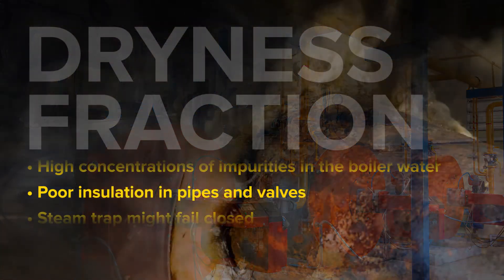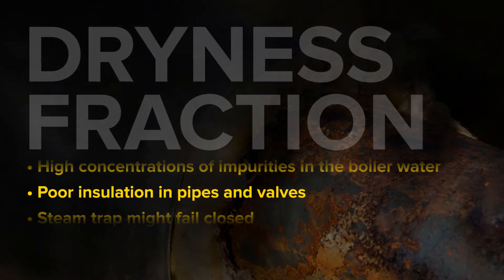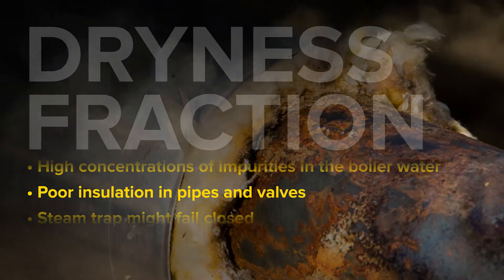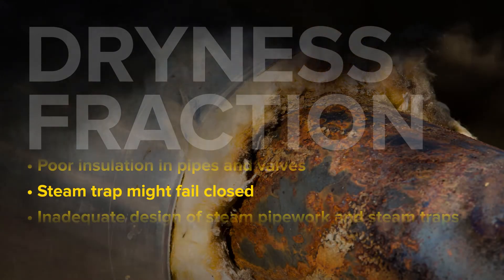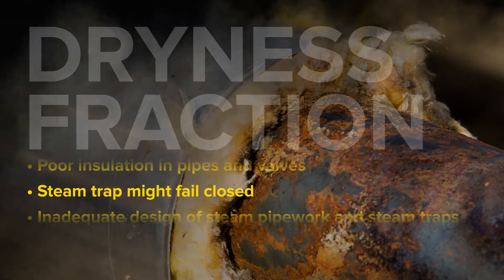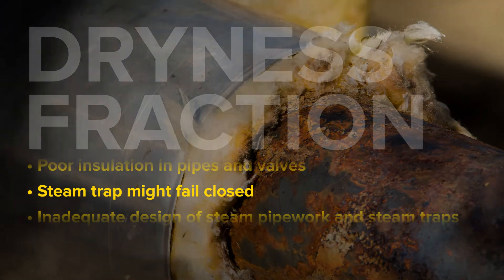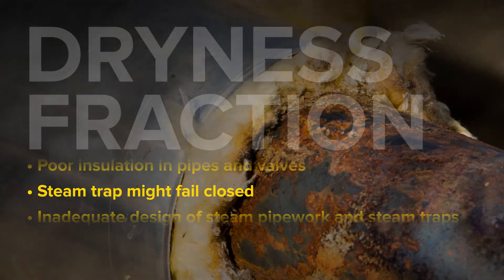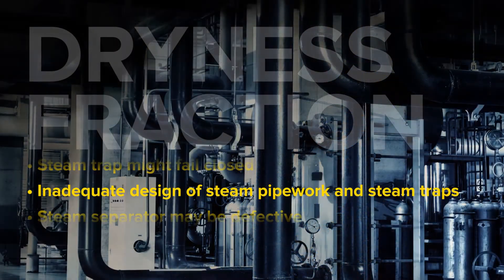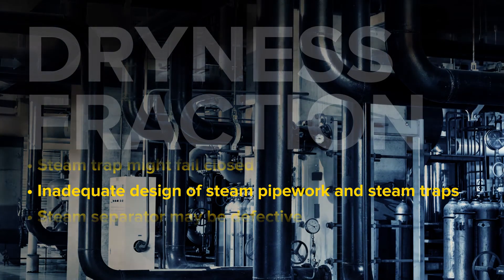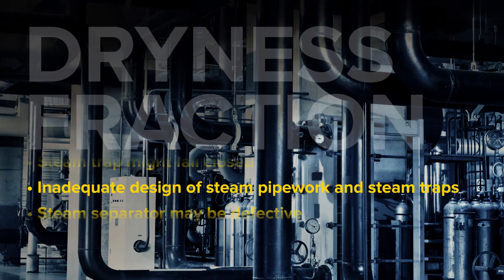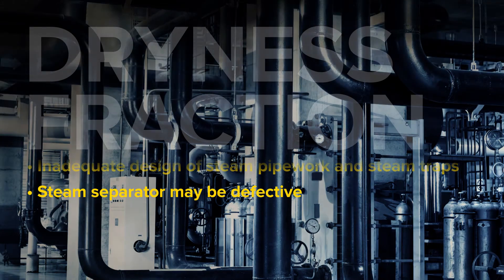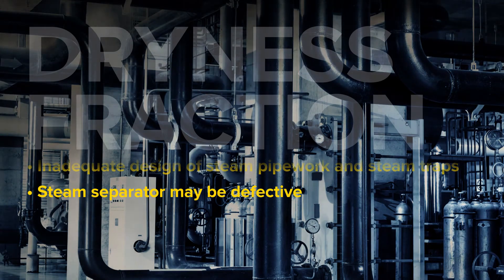Even poor insulation in pipes and valves leads to water in the steam as heat is lost and steam condenses. A steam trap might fail closed, particularly at the bottom of a separator, increasing the amount of condensate in the pipes. The design of steam pipework and steam traps may be inadequate to handle condensate, or a steam separator may be defective.